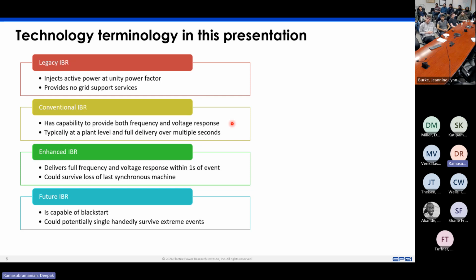Any bulk power system-connected inverter-based resource plant, maybe solar or wind, will typically have multiple units, multiple inverters, multiple turbines, and then an overarching plant controller that coordinates the response across these individual devices. It may have some optimization embedded in it, and it controls these individual devices to provide frequency and voltage response over multiple seconds.